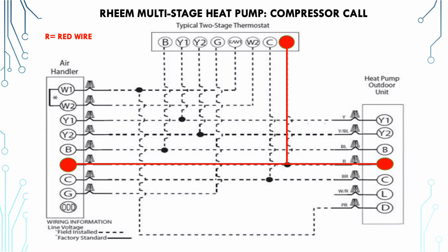And the air handler typically is also going to have a red wire. At the heat pump, it is also typically a red wire for that 24-volt connection. Now, common is blue, so you'll see a C on the thermostat, and on Rheem, it's a brown wire in the air handler and the heat pump. Different brands will use different colors. A lot of brands like to use the color blue inside the equipment for common also. So don't get locked in by colors. You want as much uniformity as you can, but when you get into the equipment, you cannot depend on the idea that this color means this.